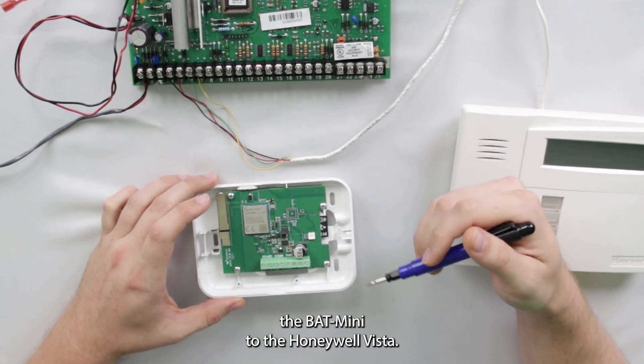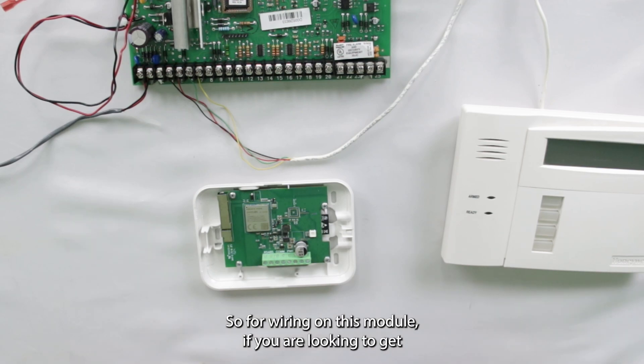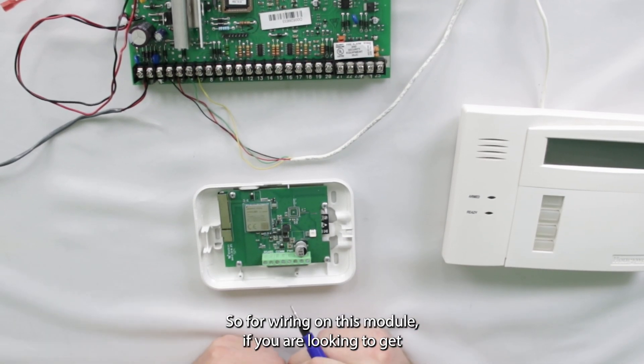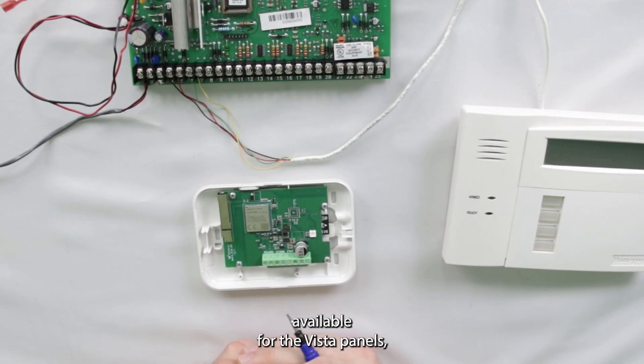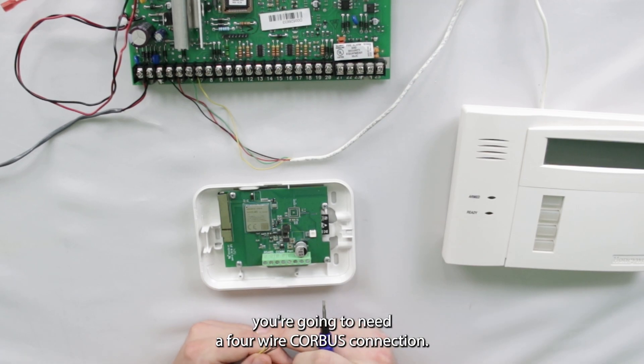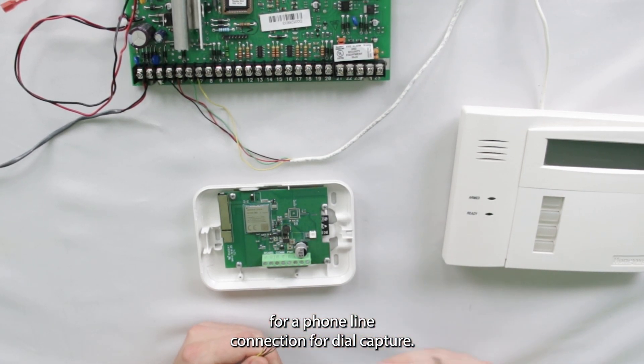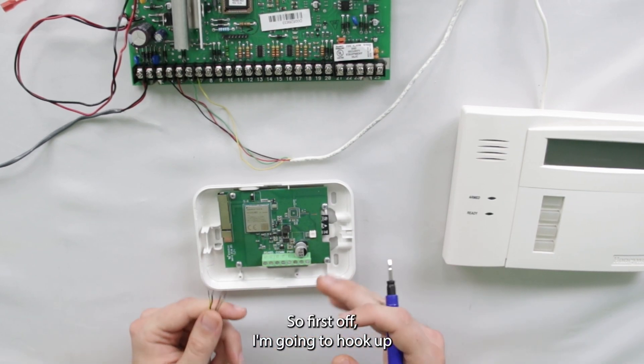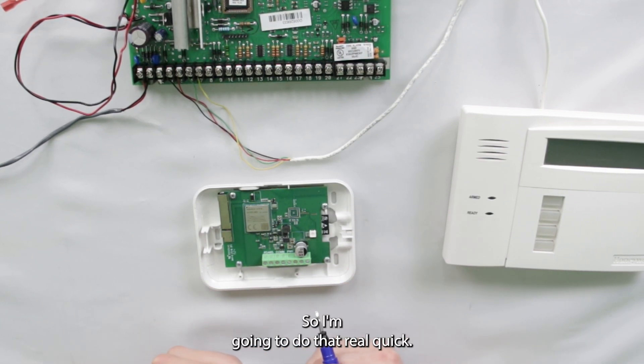Now that we have it open, we're going to wire the Bat Mini to the Honeywell Vista, and then we'll go into programming. For wiring, to get those interactive features and the integration with Vista panels, you're going to need a four-wire Corbus connection, and also two wires for a phone line connection for dial capture. First, I'm going to hook up the red, black, yellow, and green Corbus wires.